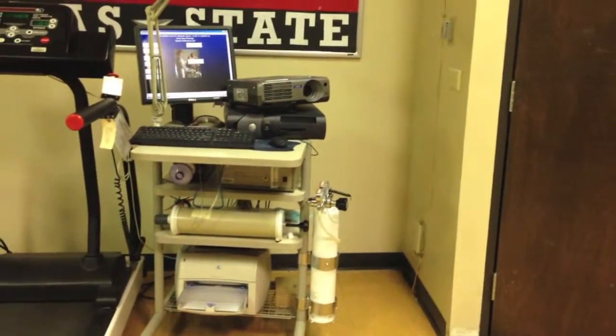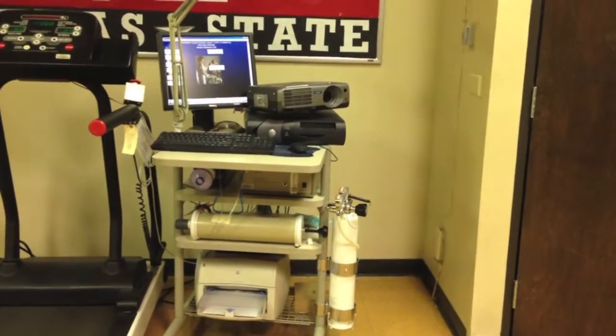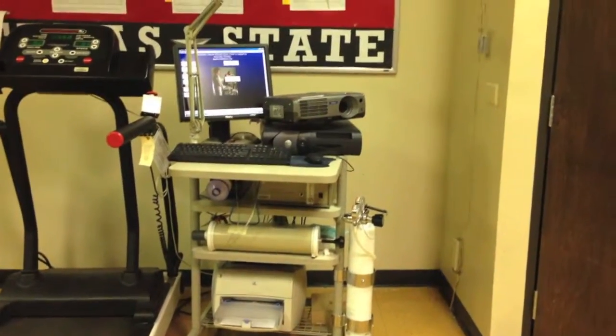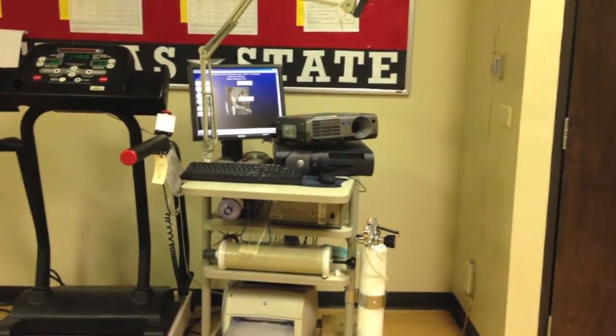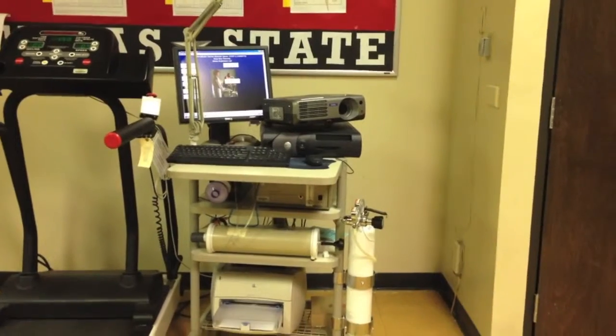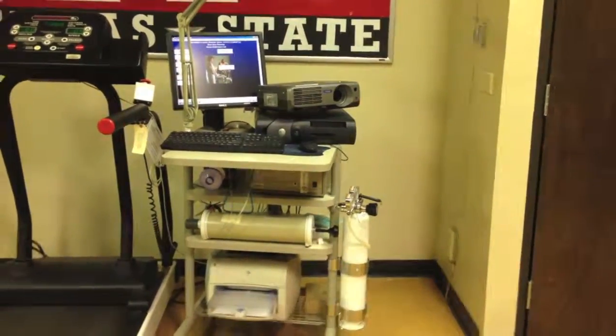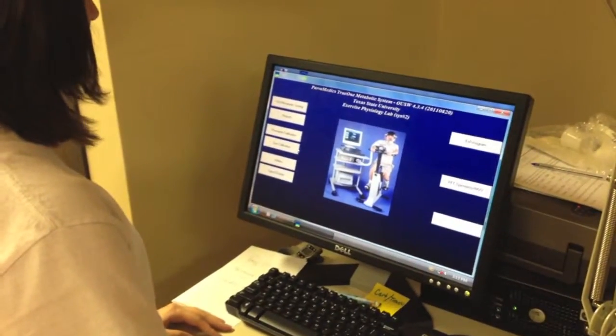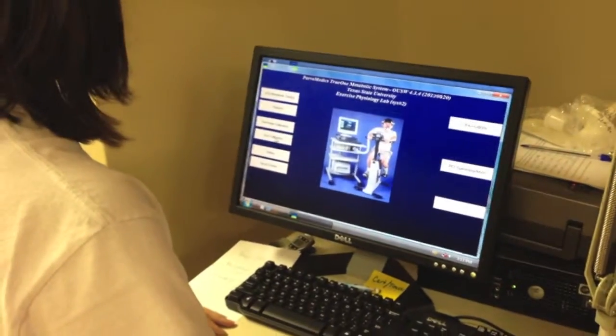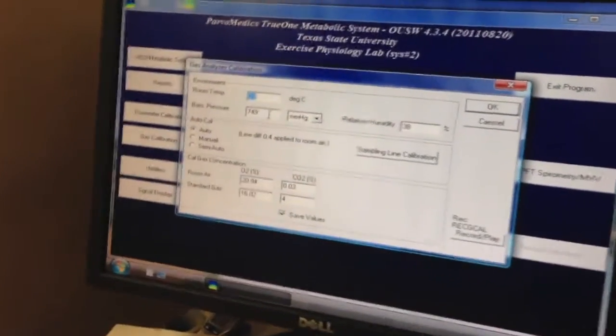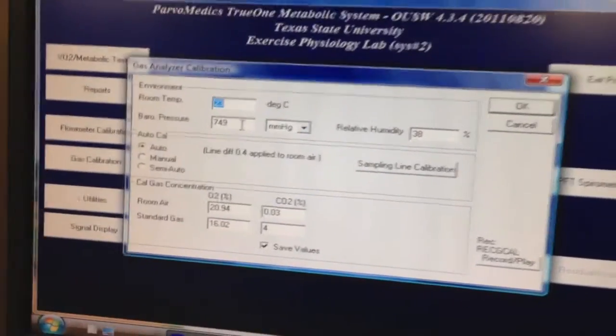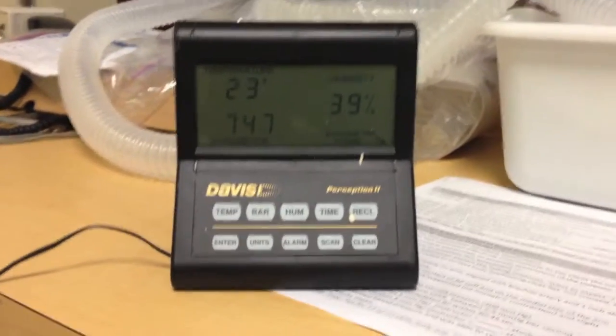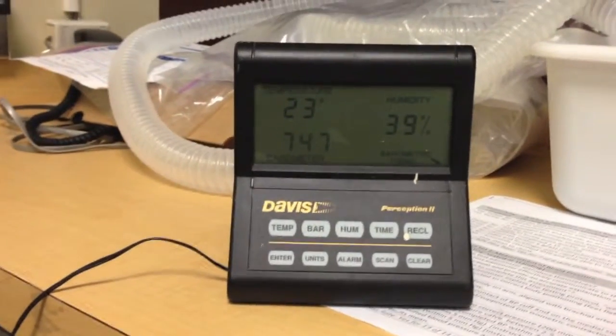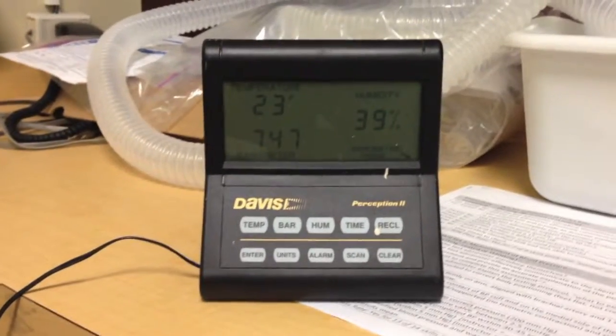For appropriate measurements, the system needs to be calibrated prior to measurement. Calibration is performed after an analyzer warm-up period of 30 minutes. Some devices use room air for calibration, which is what we will be using. The first step in calibrating the metabolic cart is to do a gas calibration, which will be testing the air in the room. Measurements are temperature, humidity, and barometric pressure, as shown here.